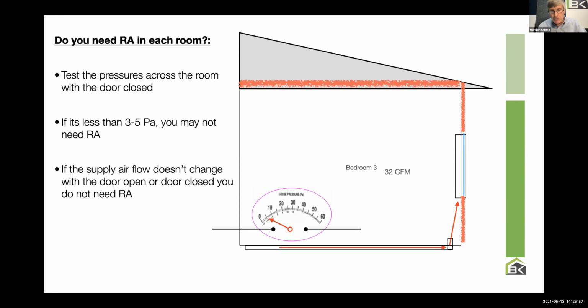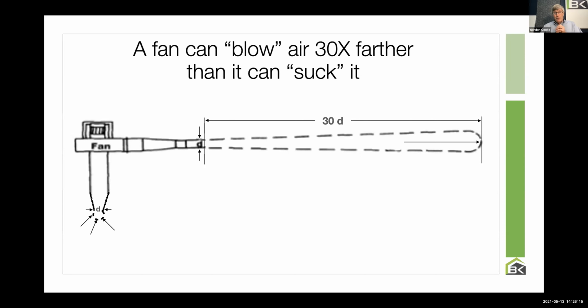Now, let's be really clear. I'm not saying you don't need return air. You need return air somewhere. You need the air to get back to the air handling appliance. You just don't necessarily need it in every specific room. And you can determine whether you need it, at least after the fact, by simply doing this measurement. And the reason for this is a fan can blow air 30 times farther than you can suck it. If you're trying to heat and cool a room, it's all done with supply. It's not done with return. Supply is more important than return. You need return. It just doesn't help you heat or cool a room more by putting in more of it if you already have enough of it.